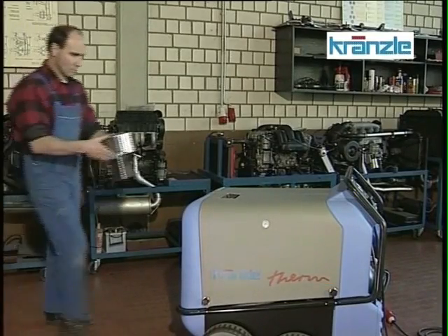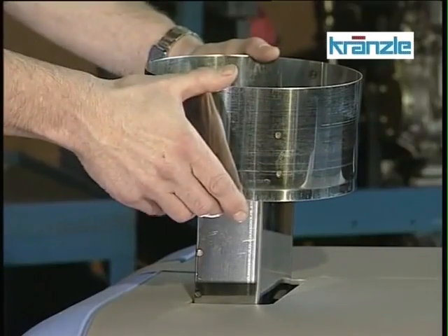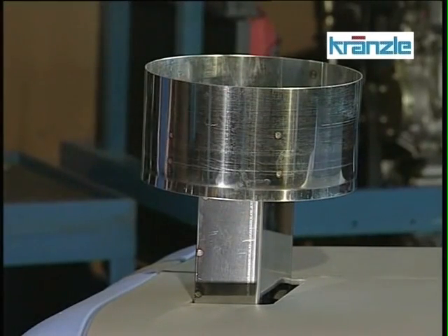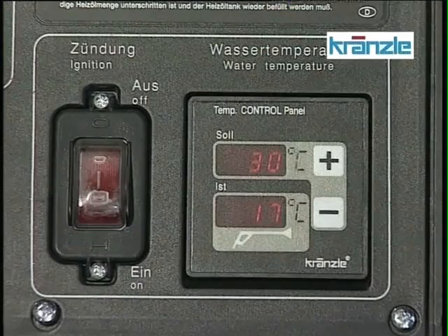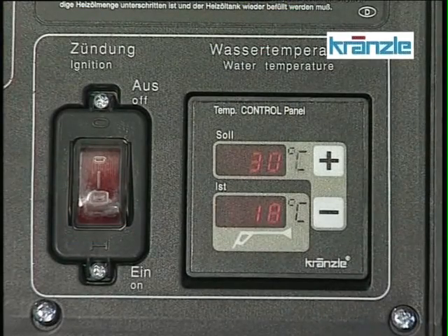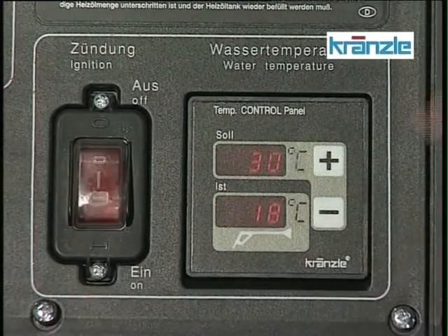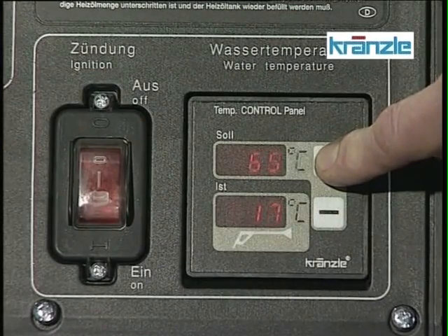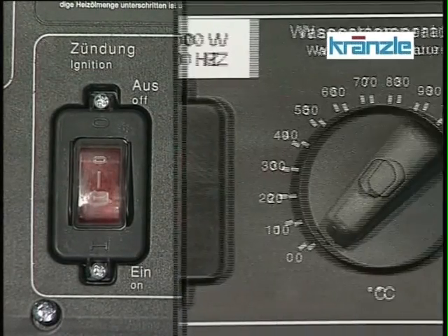If you're working in closed rooms, you will have to follow the rules concerning the extraction of exhaust gases. This adapter for the exhaust pipe can be obtained as an accessory. Now switch on the burner and set to the desired temperature, digitally with the 5 series, and with this thermostat on the 0 series.